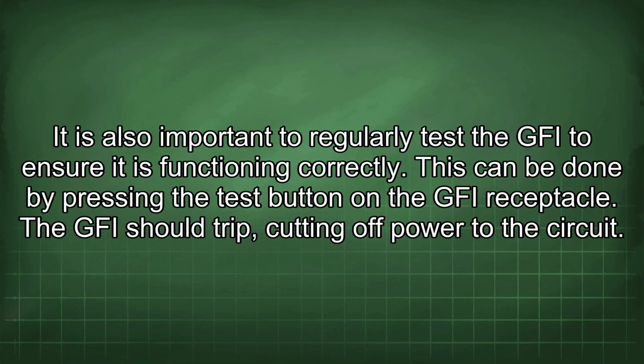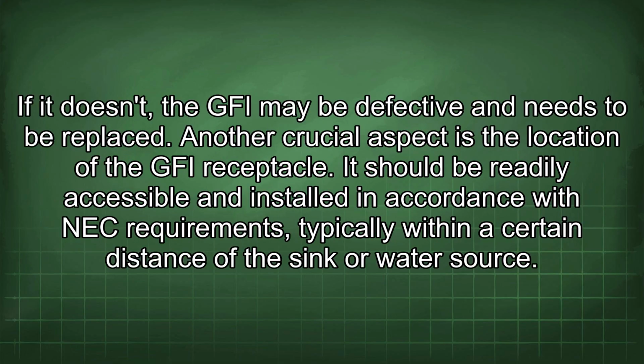It is also important to regularly test the GFI to ensure it is functioning correctly. This can be done by pressing the test button on the GFI receptacle. The GFI should trip, cutting off power to the circuit. If it doesn't, the GFI may be defective and needs to be replaced.